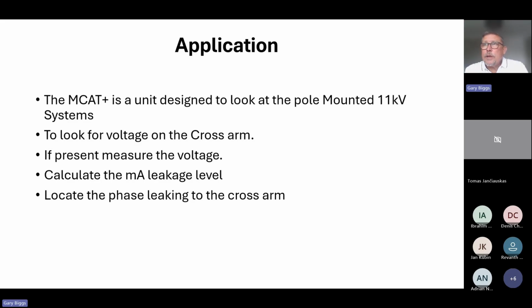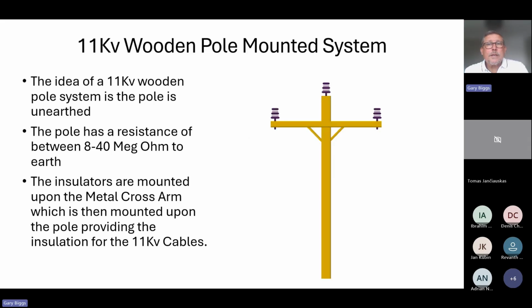So as I say, what we're going to do this morning is to start off looking at what an 11 kV pole mounted system is. If you look at any mounted system that's made of concrete or metal, you'll find that they're earthed out. So if an insulator broke down, and even if it only partially breaks down, invariably what it'll do is take out the system.